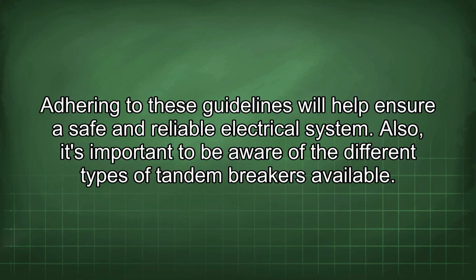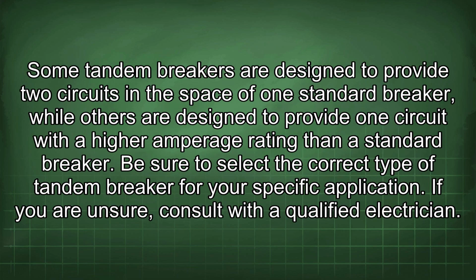Also, it's important to be aware of the different types of tandem breakers available. Some tandem breakers are designed to provide two circuits in the space of one standard breaker, while others are designed to provide one circuit with a higher amperage rating than a standard breaker. Be sure to select the correct type of tandem breaker for your specific application. If you are unsure, consult with a qualified electrician.